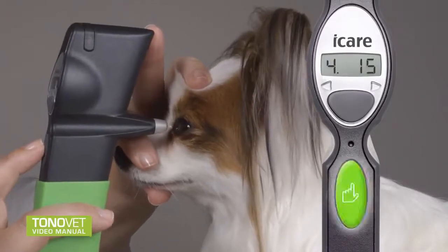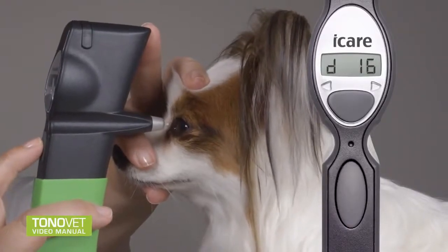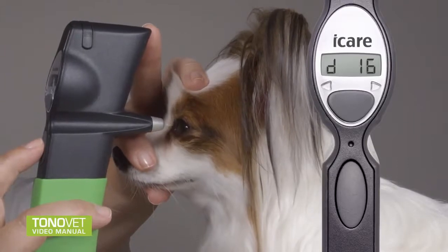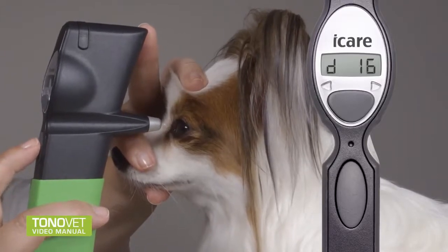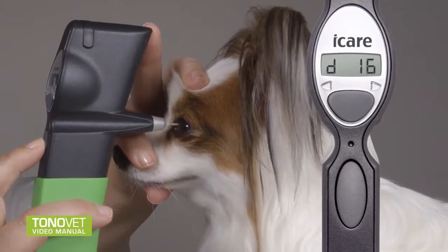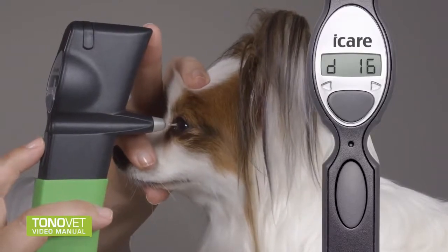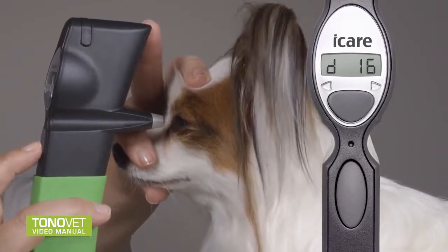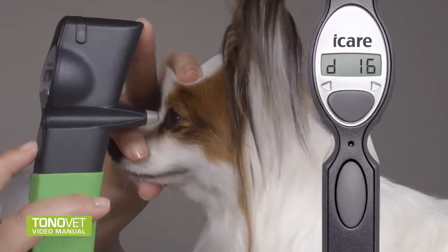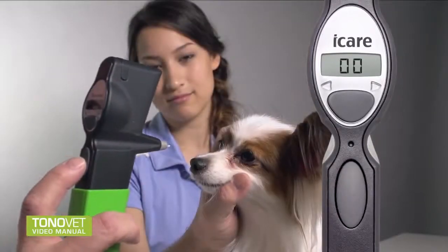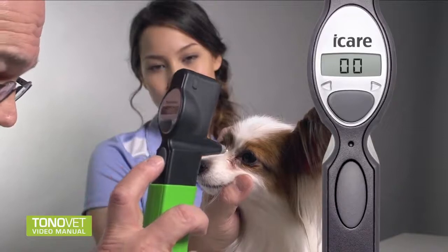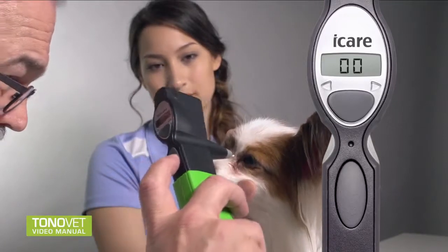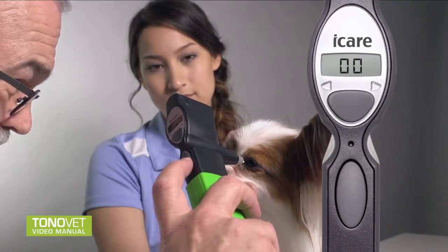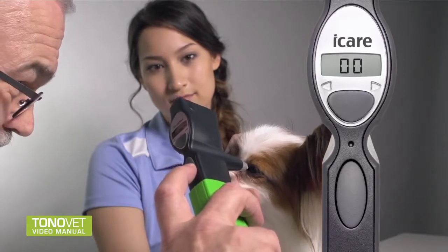After each successful individual measurement, a short beep is played, and a result is displayed. After 6 individual successful measurements, a longer beep is played, and the final result is shown on the display. A new measurement can be started by pressing the measurement button. The display shows 0, 0, indicating the tonometer is ready for the next measurement.